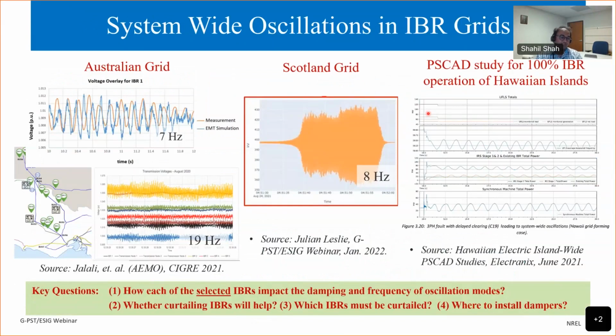For example, on the left side, you see 7 hertz and 19 hertz oscillations that have been appearing regularly in Australian power systems operated by AEMO. In the middle, we see the 8 hertz oscillation in Scotland, which was presented by Julian Leslie in a similar ESIG G-PST webinar a few months back. The magnitude was around 70 kV, so they are huge and they can disrupt the power systems.